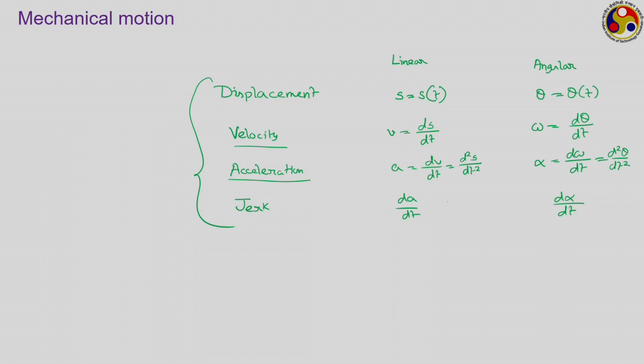For that purpose we can use two kinds of instruments: one is a vibrometer, the other is an accelerometer. A vibrometer relates to the measurement of velocity, an accelerometer relates to the measurement of acceleration. Truly speaking, a vibration pickup or vibrometer and an accelerometer have nothing different in terms of their working principle. Their major difference comes in terms of the secondary transducer used to get the final output. Generally all these devices have two transducers in sequence: a primary one and a secondary one.